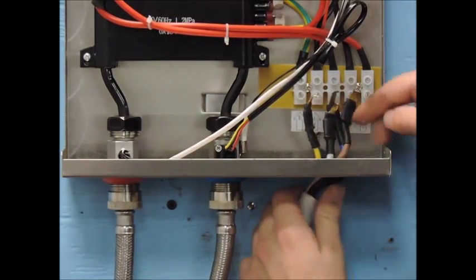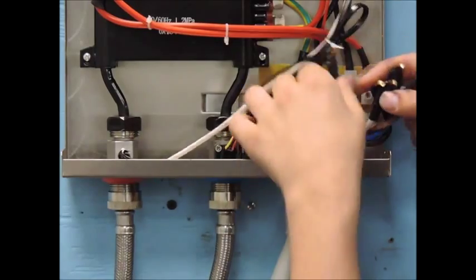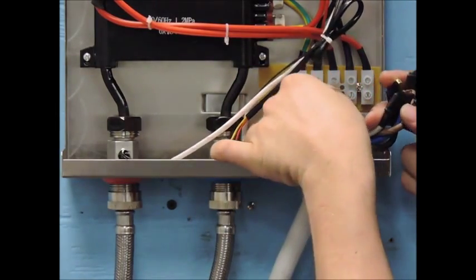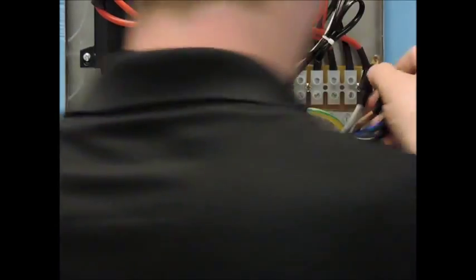In this video, we will wire the ECO 180, and we are using a specialty cable to make the explanation easier to understand. The port in the terminal block to the farthest left is the terminal for your ground wire, labeled E, and should terminate at the grounding bar in the breaker panel.